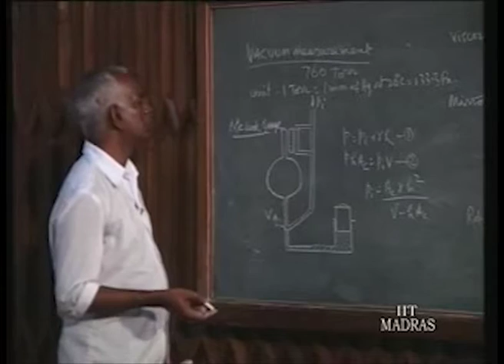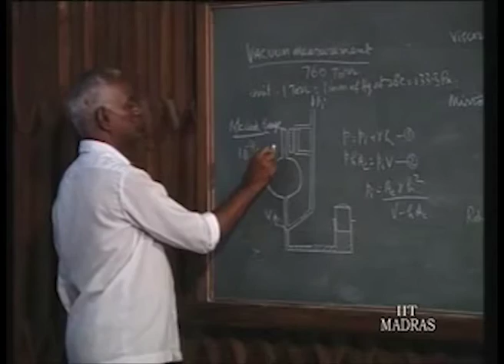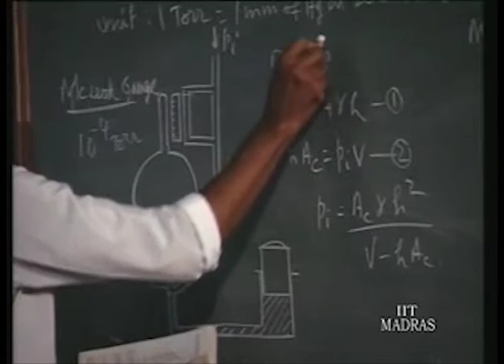For calibration purposes, people go for this McLeod gauge, which can measure up to 10 to the power of minus 4 torr. It is mainly used for calibration because the measurement principle is based on Boyle's law, that is P1 V1 is equal to P2 V2, which is made use of here. So it's used for calibration purposes.